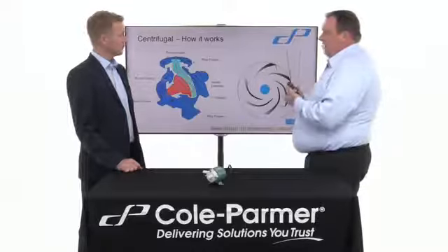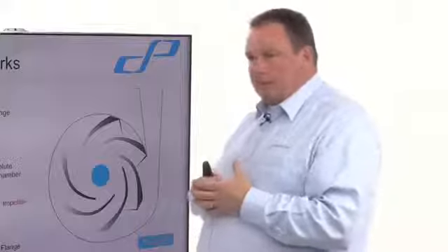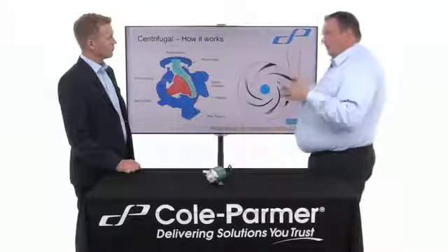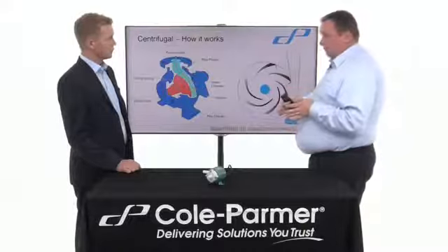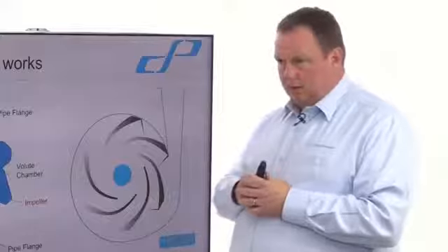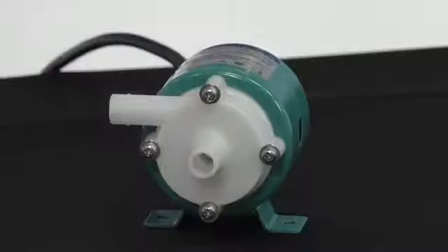They're very, very good. They can handle the solids with the recessed impeller that I was talking about. Yeah. They can handle abrasives. They have many variants in terms of materials, because material science has come a long way. Traditionally cast iron. You've got cast iron, stainless steel. You can get phosphor bronze for seawater, things like that. They can make them out of plastics now, or plastic coated is the big thing. So they can actually coat the internals in plastics, so they can cope with some of the more aggressive chemicals. They can use other treatments like nitriding treatments to cope with abrasives and things like that.